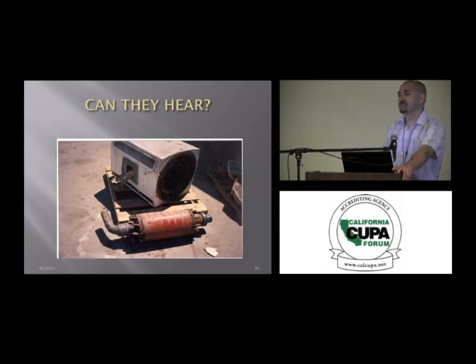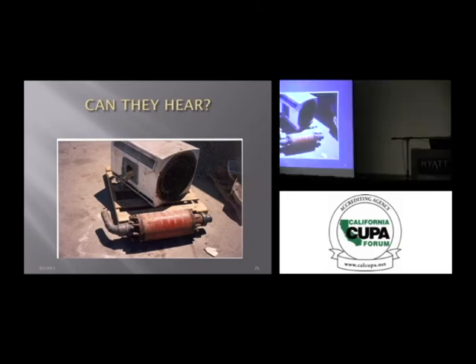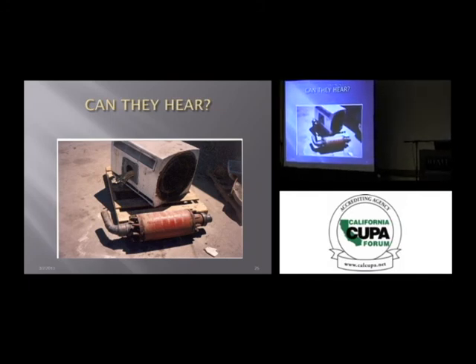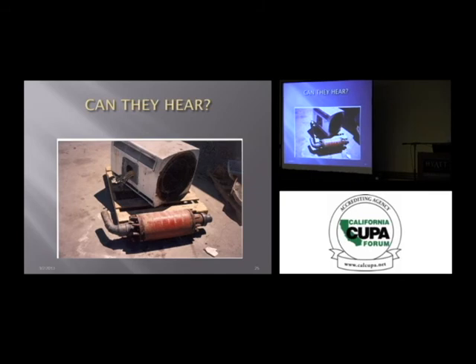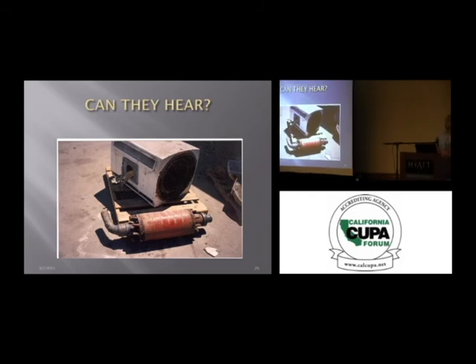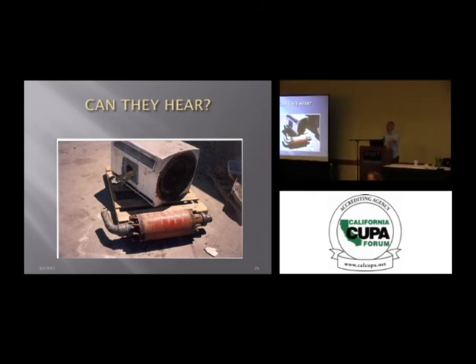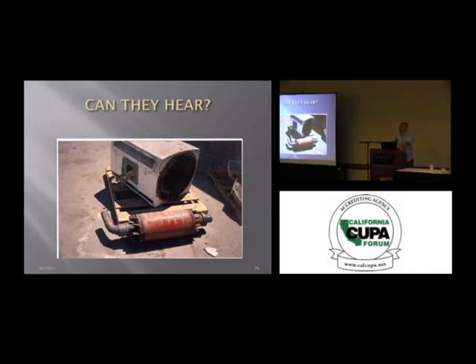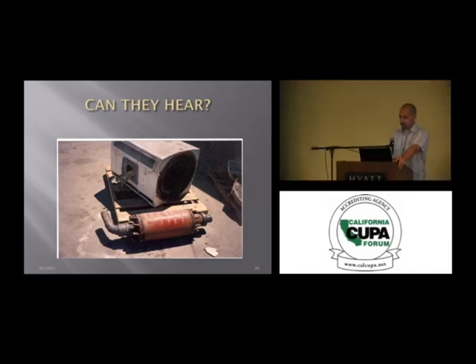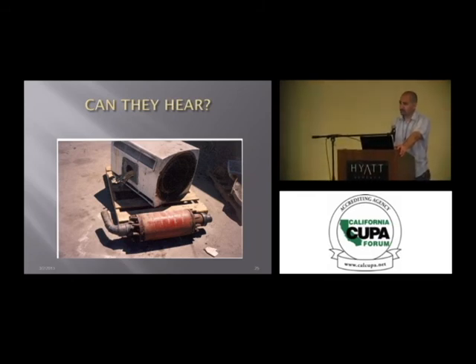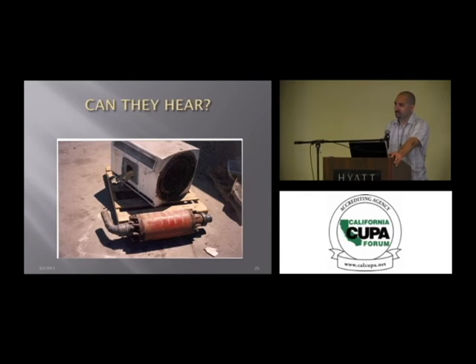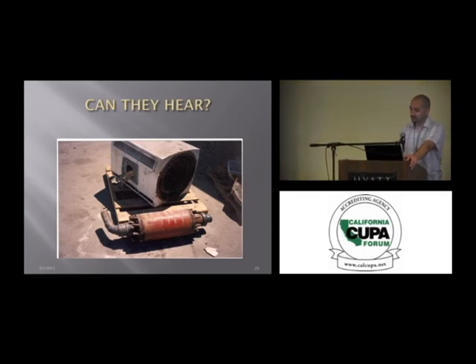Basically, it was one of those things that they just started and ran, and when things don't make noise, that's when they get attention. Okay. And so here is a lubrication problem on the bearing, and over time, it started to seize up, and it heated that shaft up so much that when it finally let loose at its coupling, you can see that the laws of inertia are correct. It will throw it 90 degrees to its rotation. That's the first time I've seen a motor shaft in refrigeration turn like that. That bearing had to be making noise for a long time. That's why we do bearing analysis, that's why we do our annual inspections, and that's why we use our ears as we walk through the plant.